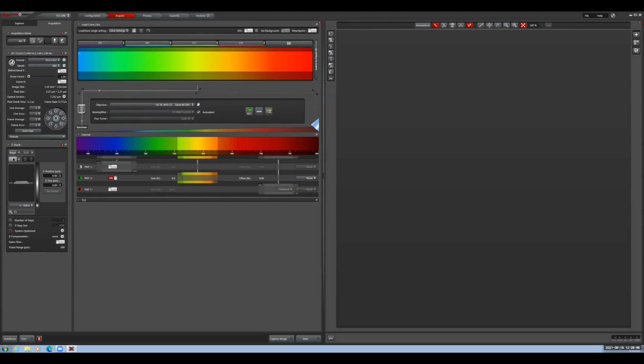Okay. So to find the sample, we need to do Z stack or Z position. And down here, for whatever reason, it starts at Z Galvo. We don't want Z Galvo. So change this under Z stack to Z wide. Now I can move the stage with the computer. The objectives can focus up and down with the computer. Okay. We are on 10X here. If we wanted to have a different objective, we would change it here.